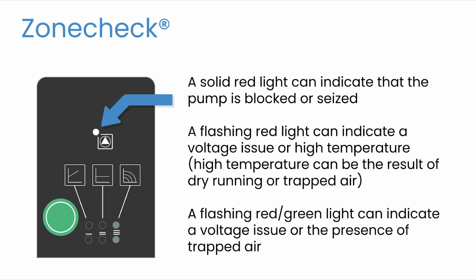The pump also displays lights which can be helpful to indicate and diagnose faults. A solid red light can indicate that the pump is blocked or seized. A flashing red light can indicate a voltage issue or high temperature, which can be the result of dry running or trapped air. A flashing red-green light can indicate a voltage issue or the presence of trapped air.